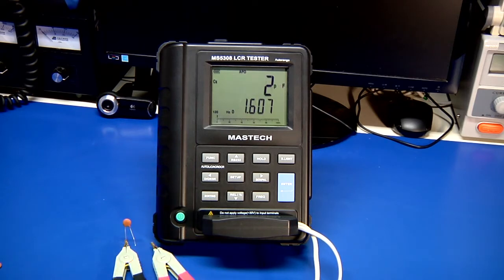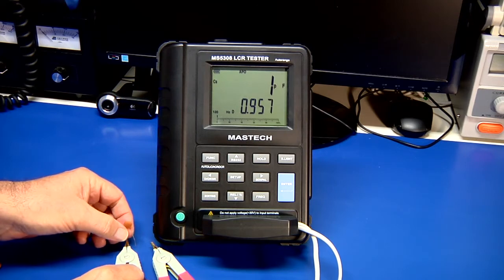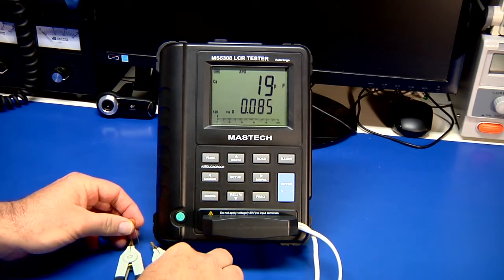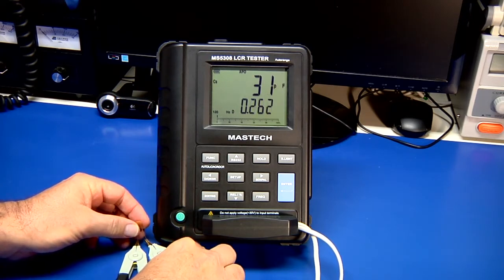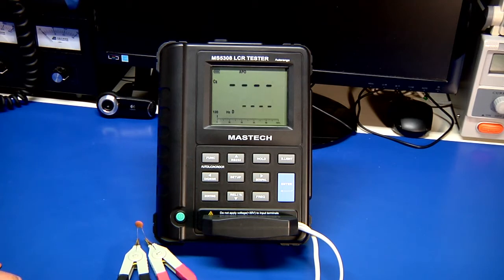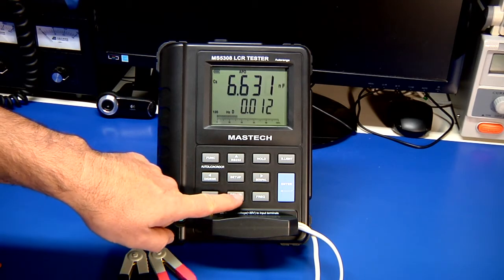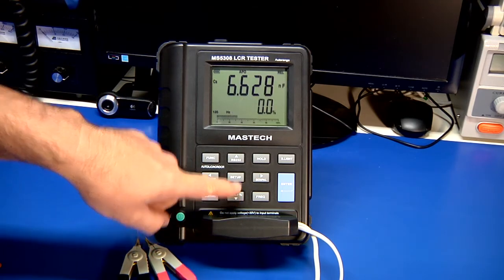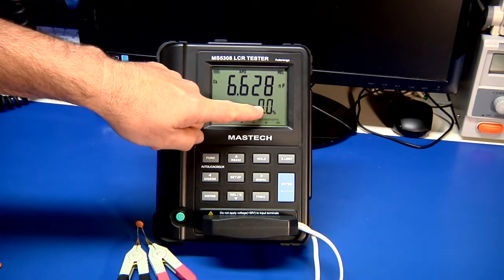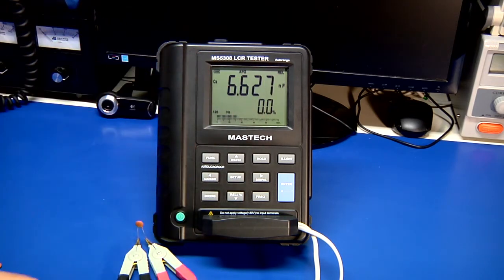Now we're back into normal measurements. To use the REL mode, you just take a capacitor that you'd like to be the standard. Here I've got a capacitor, you simply clip it in like you're doing a normal measurement. Once that's selected, just press the REL key. You'll get a REL, and then you'll get a percent difference from that value that you selected.